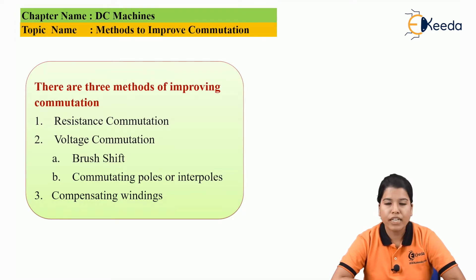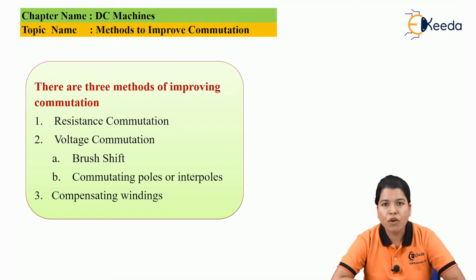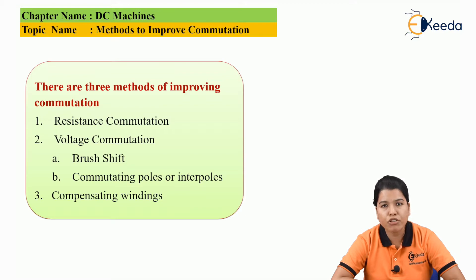Now, in the case of resistance commutation, whatever brushes are used in the DC machine, the resistance of those brushes must be increased. Hence, we have to use high resistance carbon brushes. Due to this, whatever sparking occurs in the process of current reversal is eliminated, and we can improve the method of commutation.